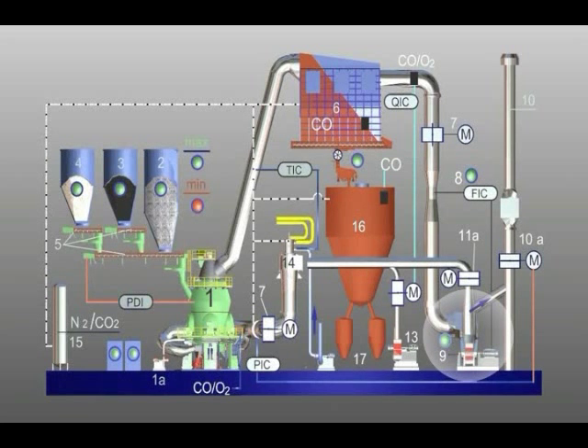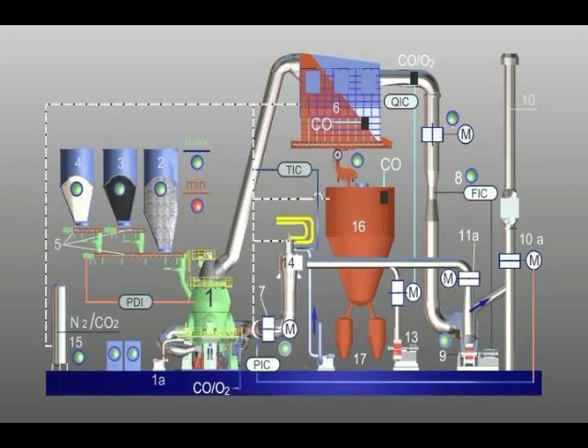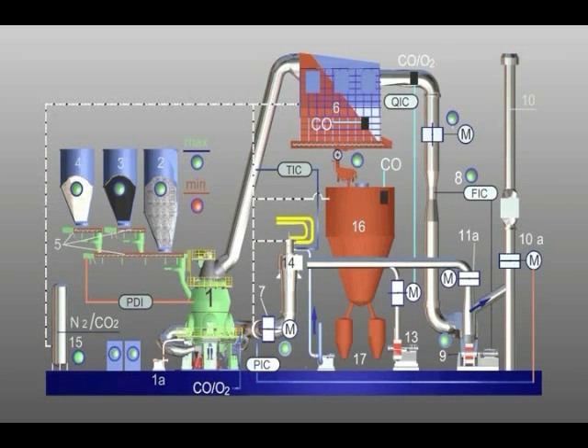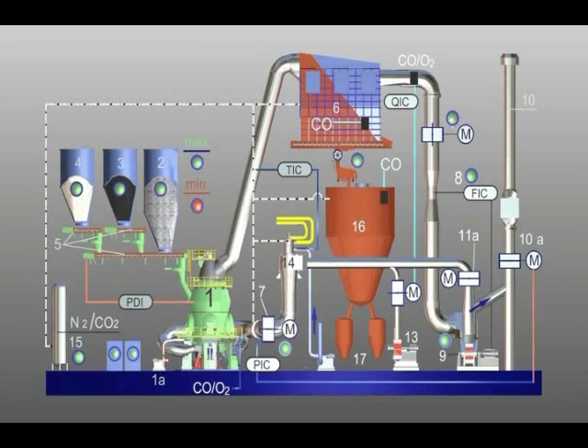The process gas fan, position 9, is started up and operated with a minimum volume flow. The plant is inertized by feeding in nitrogen or carbon dioxide from the corresponding dispensing vessel, position 15.